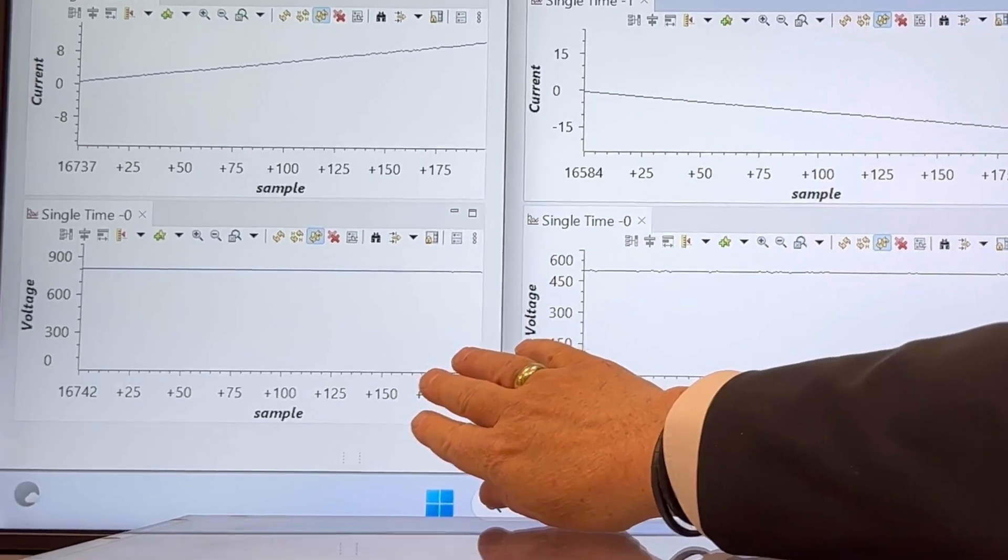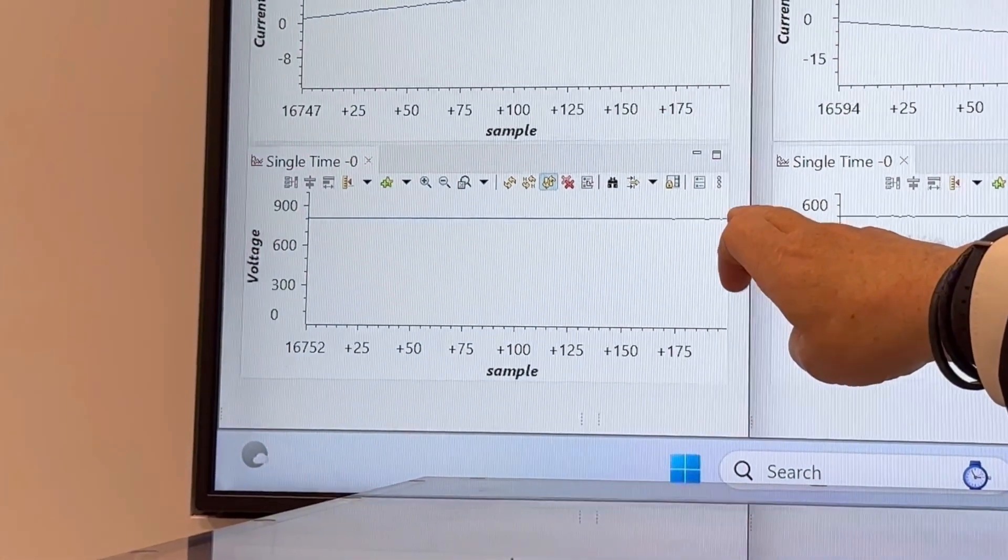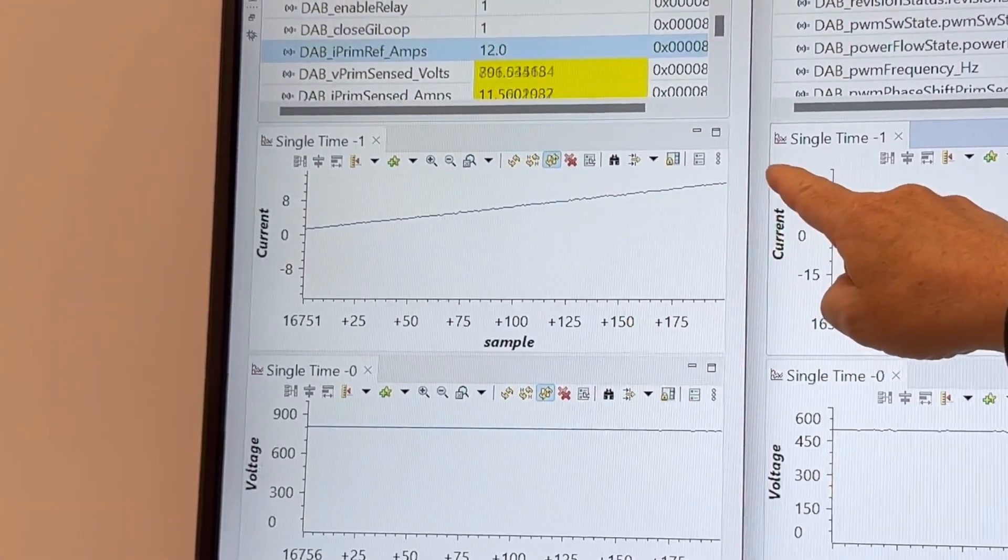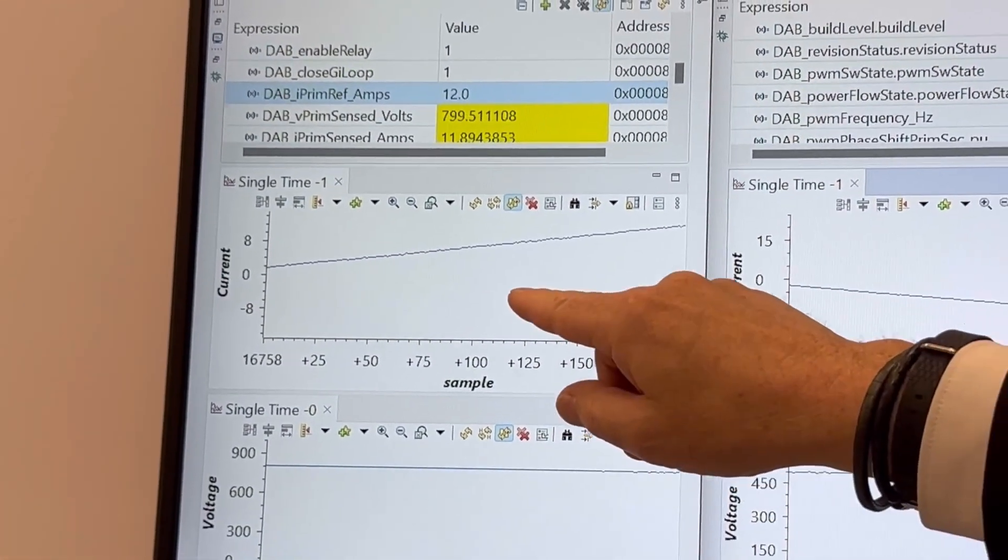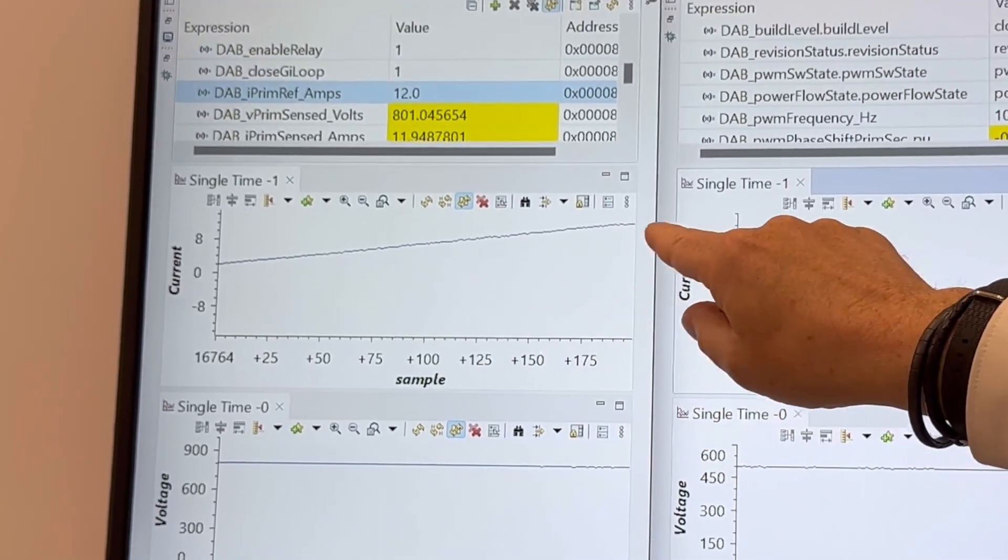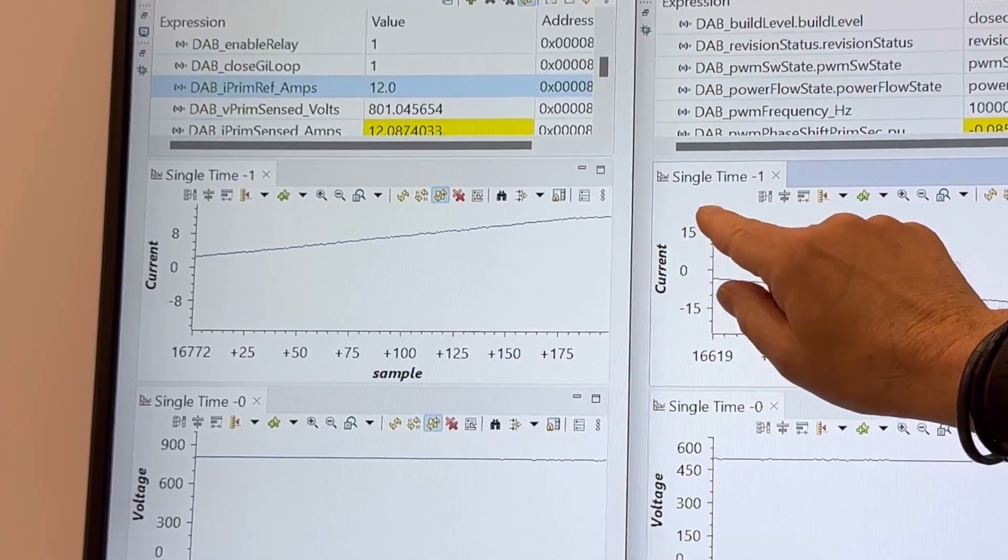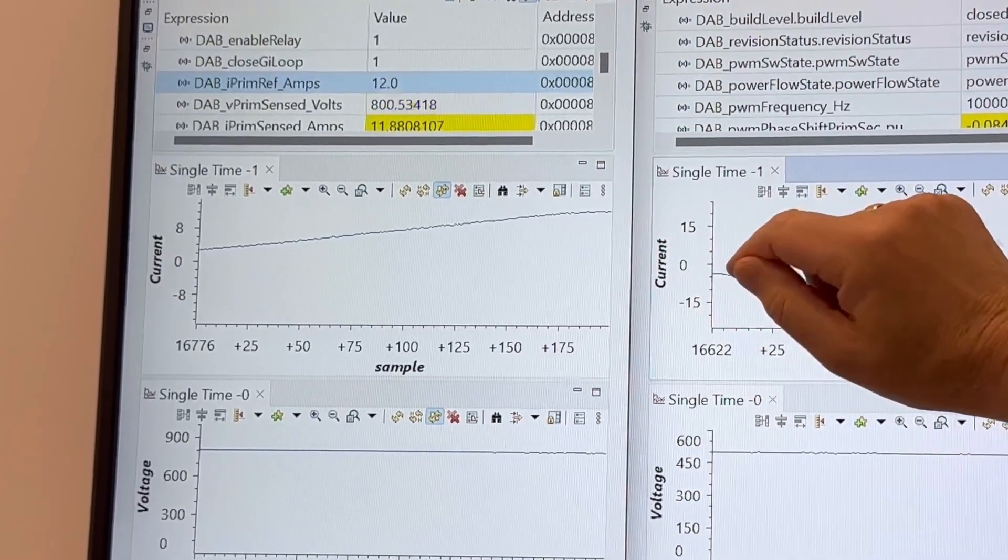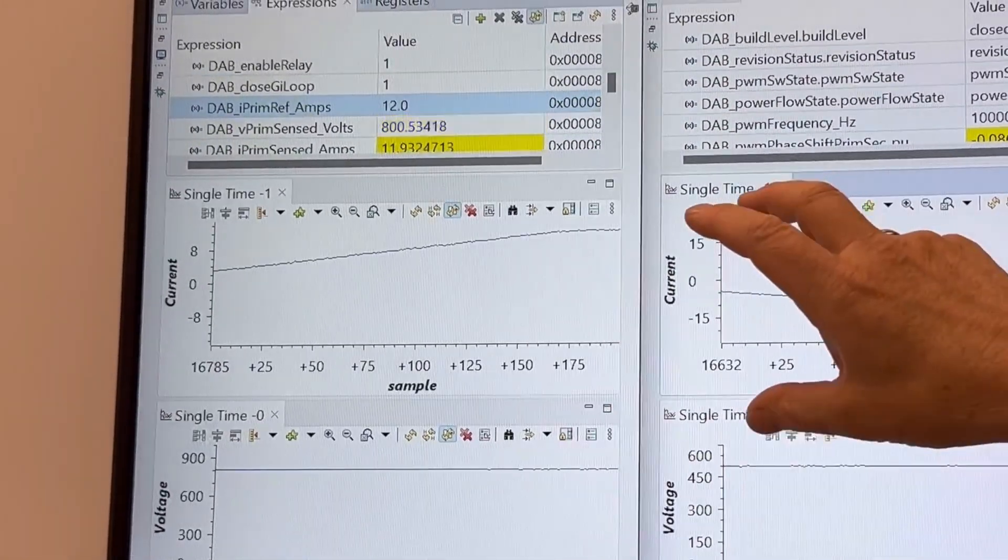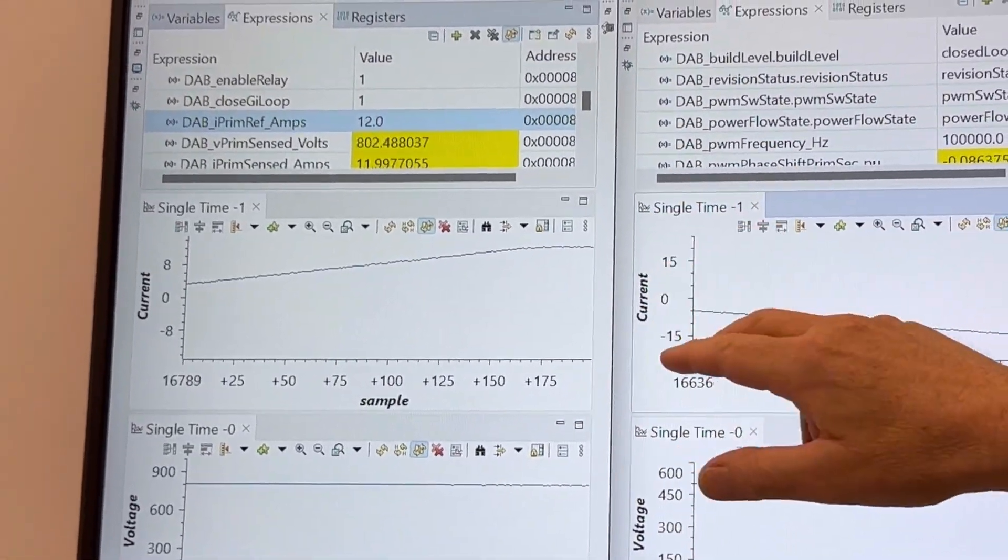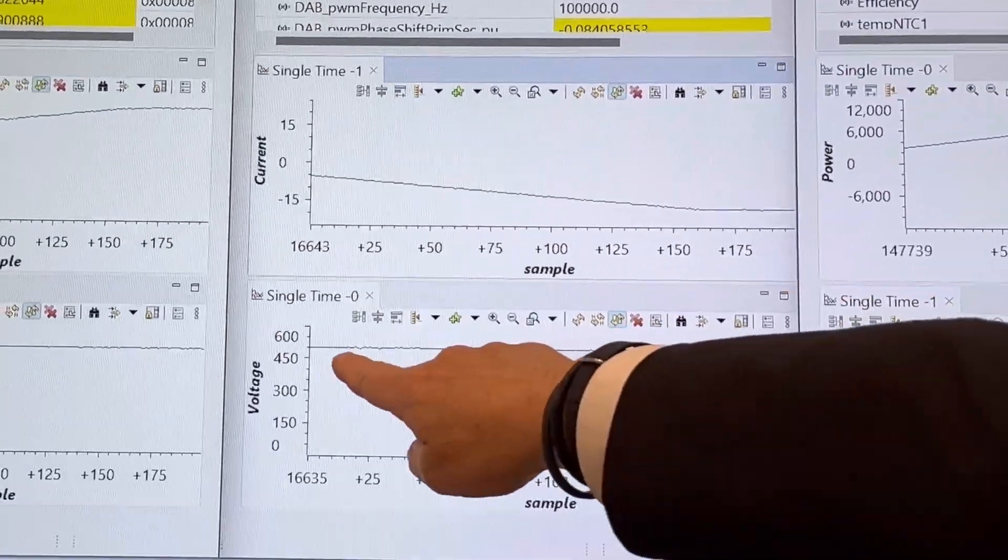We have here on the left side the input side reflected, the input side 800 volt DC bus voltage at the input. The current is ramping slowly up. We started that half a minute ago, going from zero amps all the way up. We are currently already at 12 amps almost. So that means at 12 amps 800 volt, this is 10 kilowatt what is going into the converter.